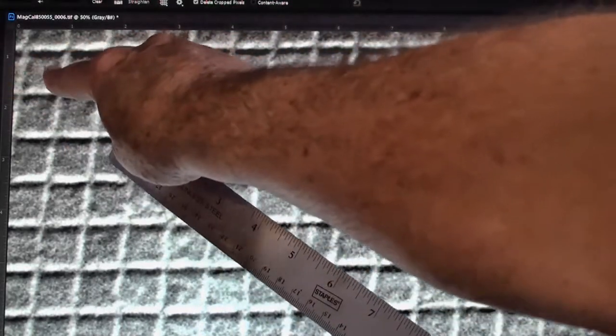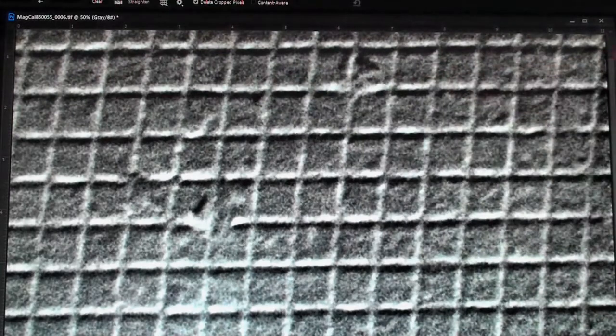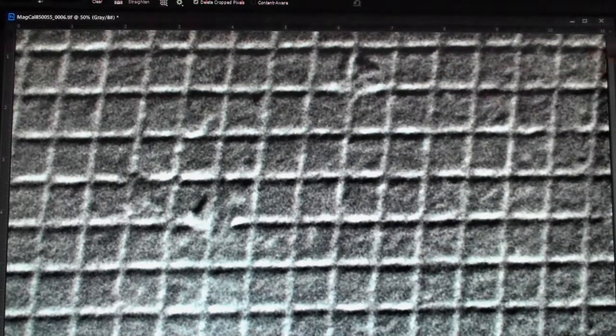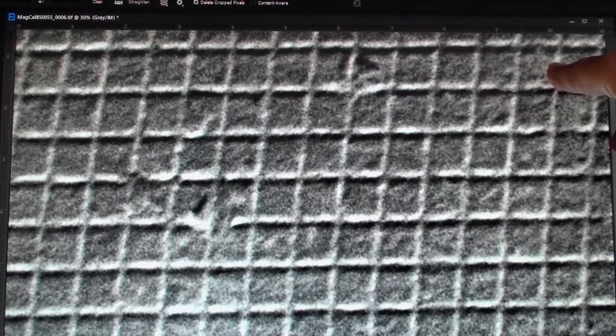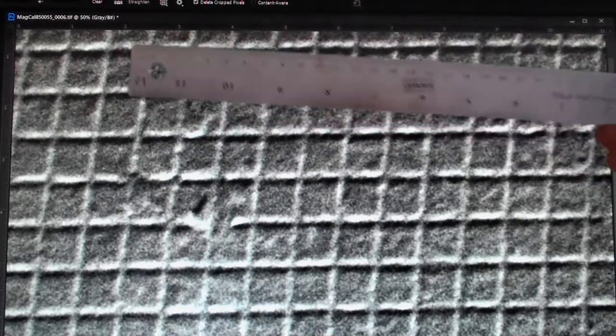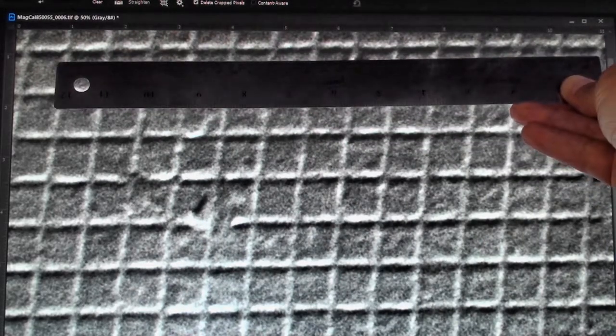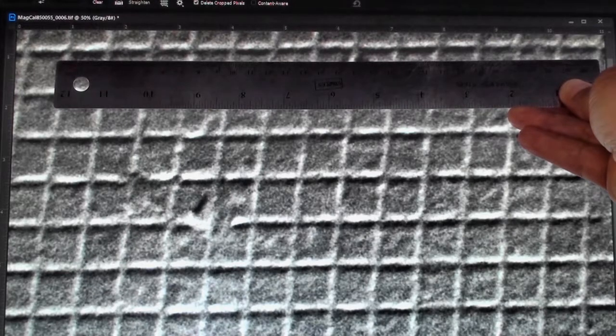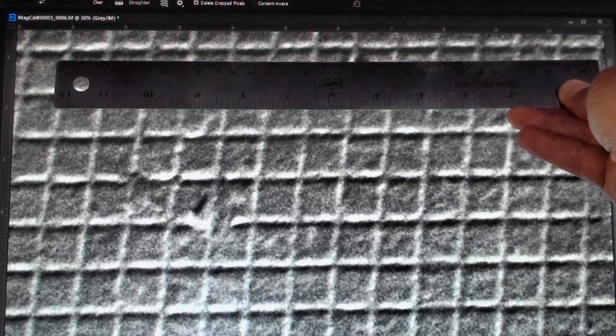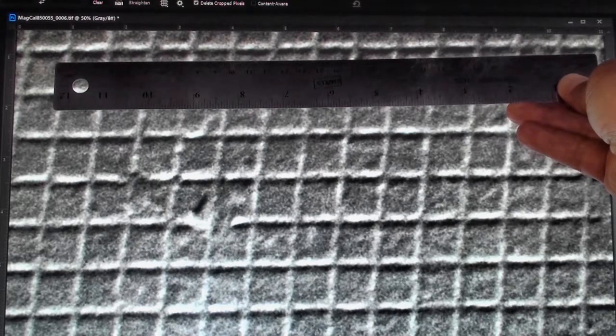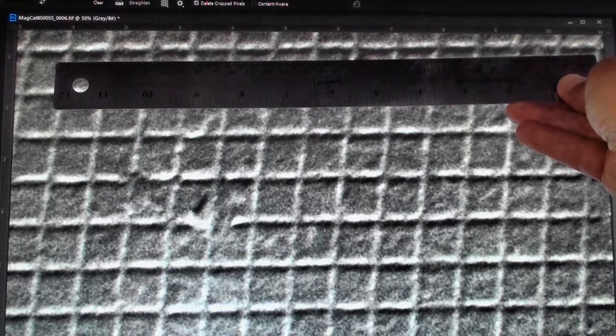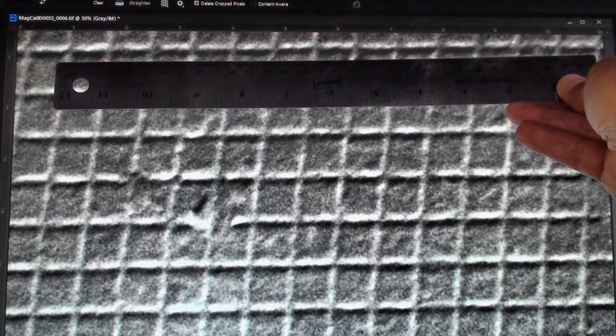When we perform a calibration, we want to be sure to measure as many squares as possible. And we only want to work with entire squares. We don't want to interpolate between the end of one or in the middle of one. So I'm going to start from the first full square and measure from the beginning of one square to the beginning of another square at the far end.